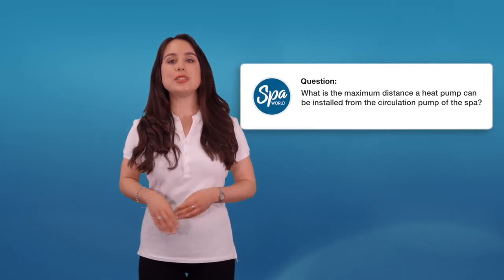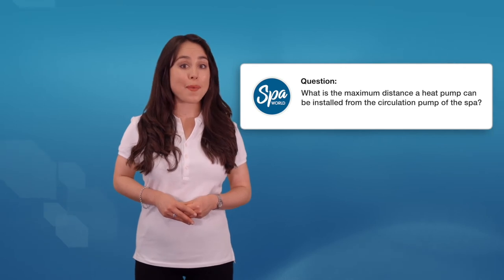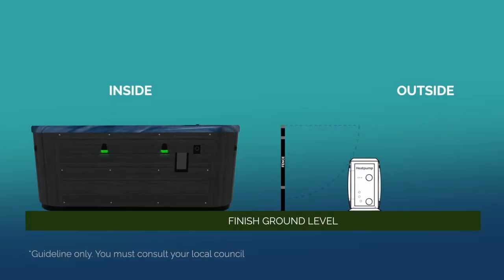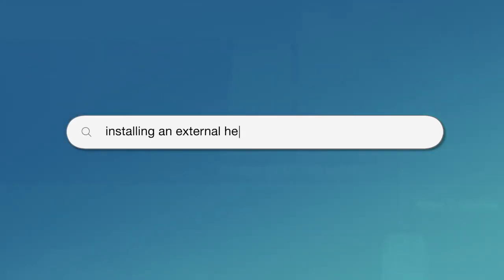What is the maximum distance a heat pump can be installed from the circulation pump of the spa? We recommend that the distance between the heat pump and circulation pump should be no greater than 3 metres. The height distance between the two pumps should not be any greater than 1 metre. And to learn more, we recommend that you read this article.